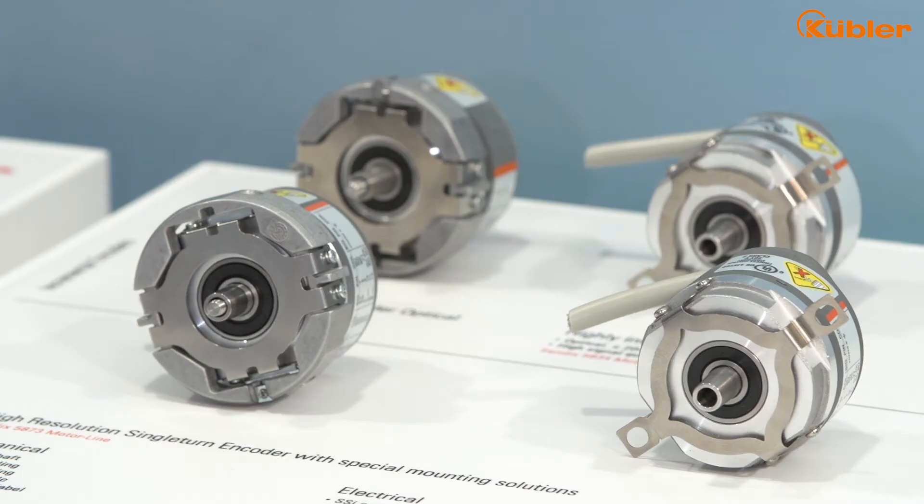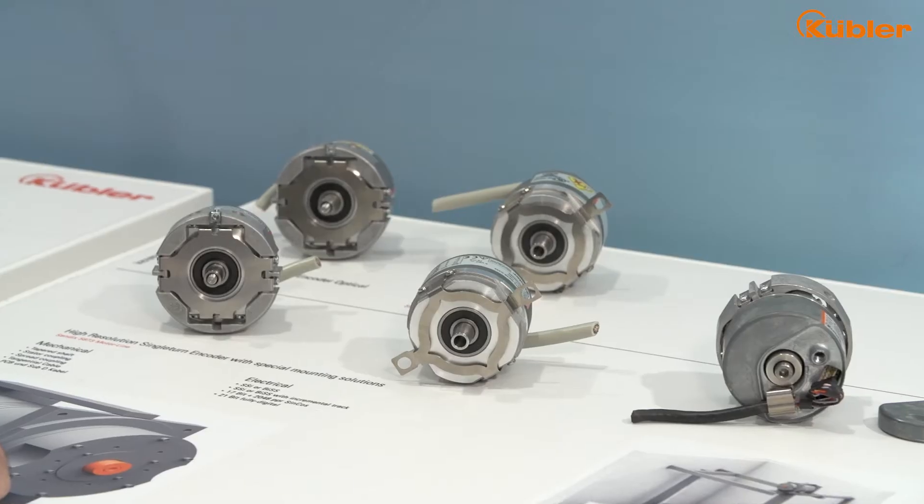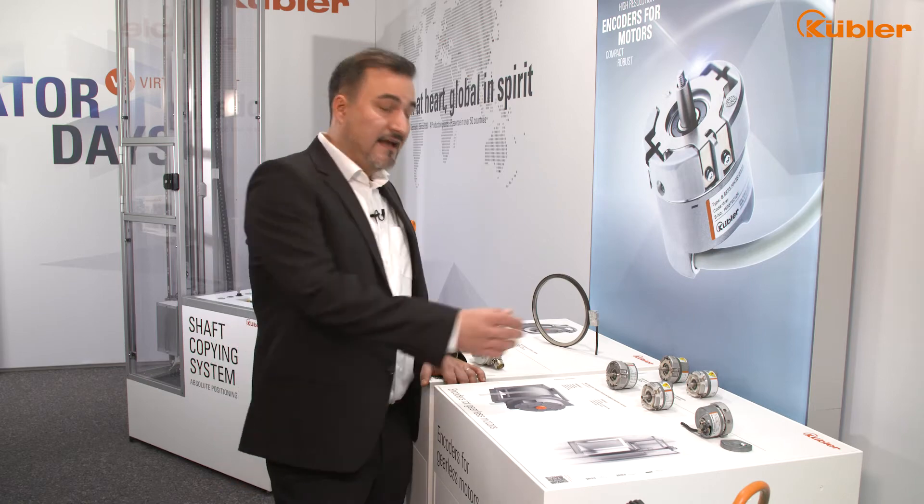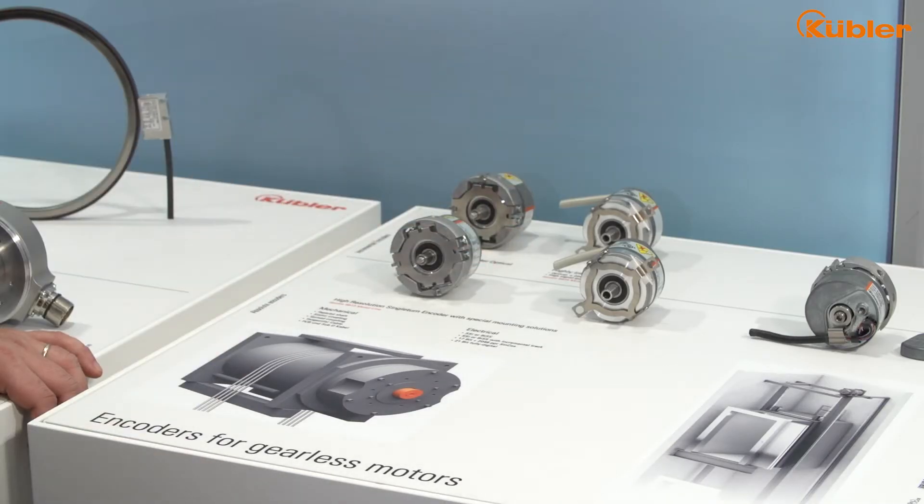With its smooth running characteristics, its high torque and low rotary speed and compact design, the gearless drive is perfectly suited for elevators. For the gearless drives, Kübler is offering a wide encoder portfolio in terms of the appropriate encoder technology, mechanical mounting concepts, and appropriate electrical interfaces. Typical for gearless motors is a rotary encoder with tapered shaft and spreading or stator coupling for the mechanical connection. Also typical is the speed control via sin/cos signals and a digital interface such as BiSS for commutation.